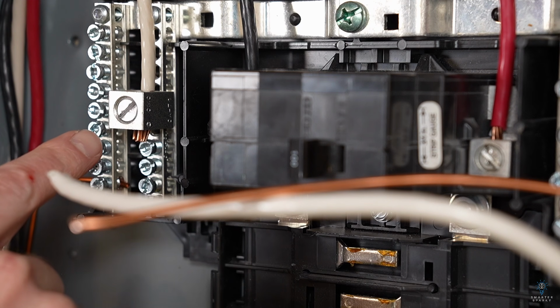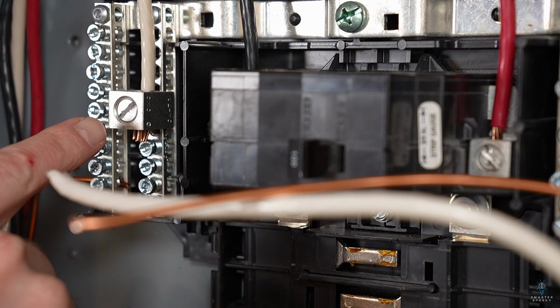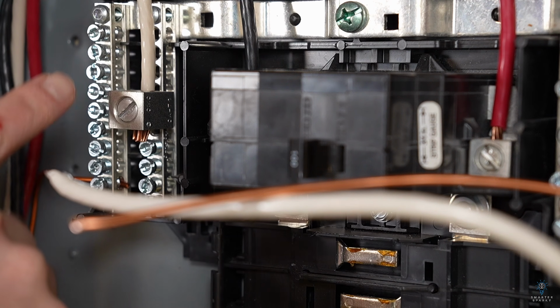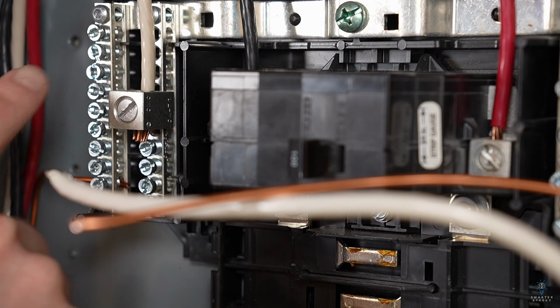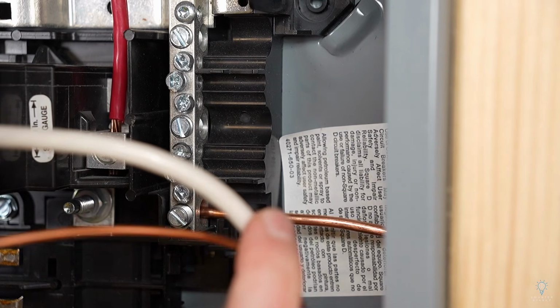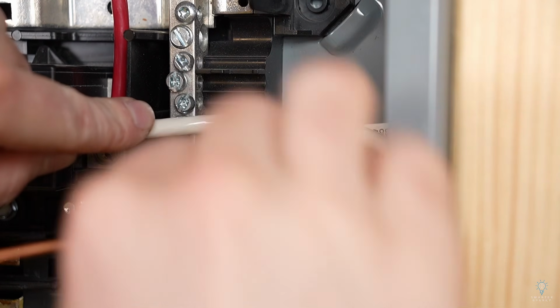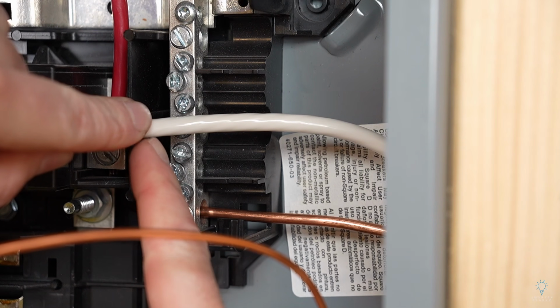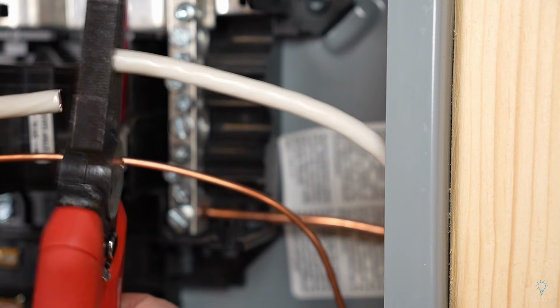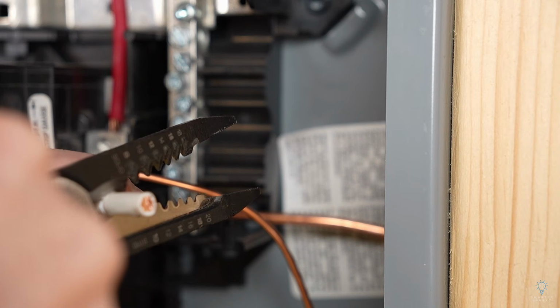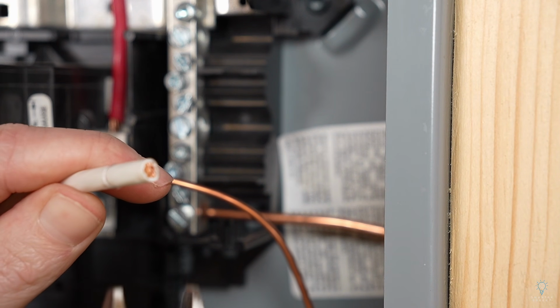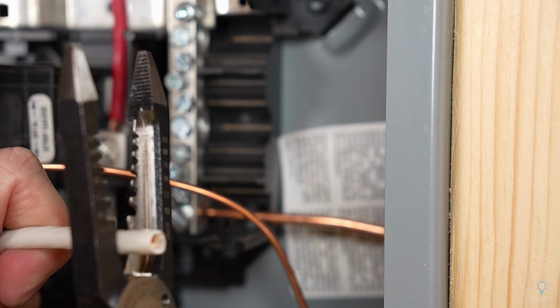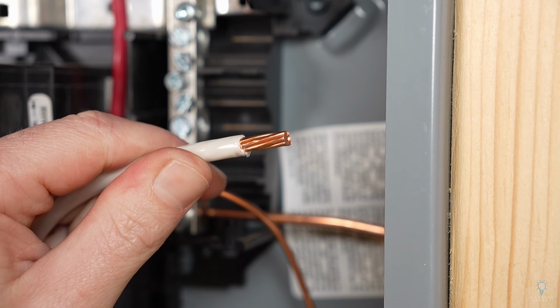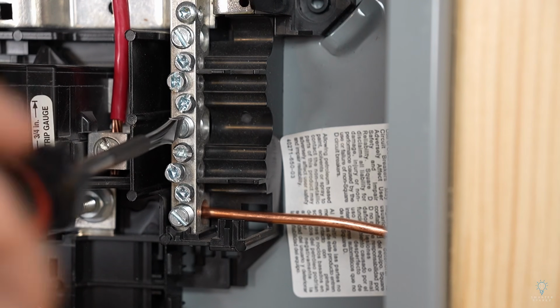If you are running a larger sub panel, you might need one of these add-on lugs that will bolt onto your bus bar so you can land a larger wire on it. So I'm going to start by landing the neutral wire, and just like before, we're going to hold it roughly in place about where it needs to be cut. We can cut it to length and strip it out. And again, I'm just using the wire cutting portion. I'm putting very little force on it, just enough that I know I can cut through the insulation, and then I can peel it off like so. And then we can install it on the bus bar.